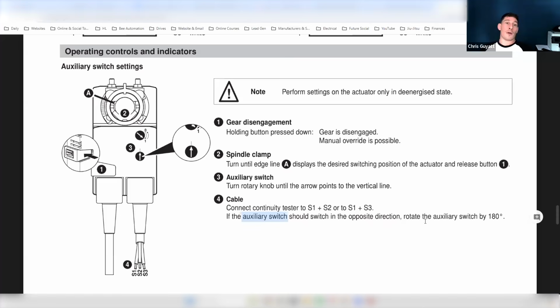What might be more familiar to some of you is if we look at a basic heating or hot water system in our homes, we've got a valve. It would be difficult for me to explain this without drawing it, but basically we send power to those valves, and when they fully open - like we send say 230 volts to this valve in our hot water system - once that valve fully opens, our auxiliary switch on that valve will then close, which means we can send that signal, the signal that tells us that valve is fully open. We can then use that signal to trigger the pump in our hot water system.